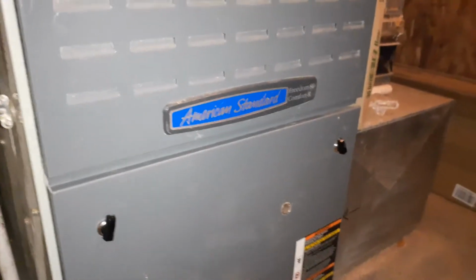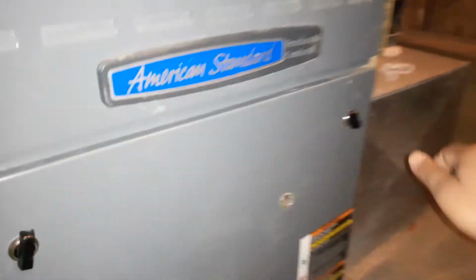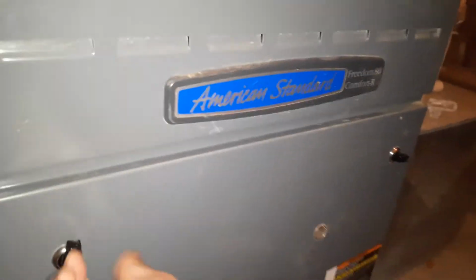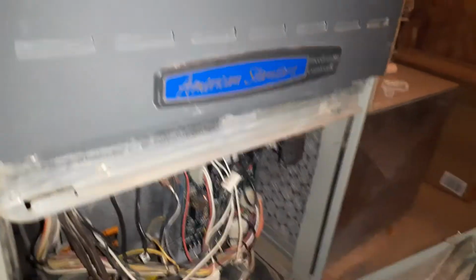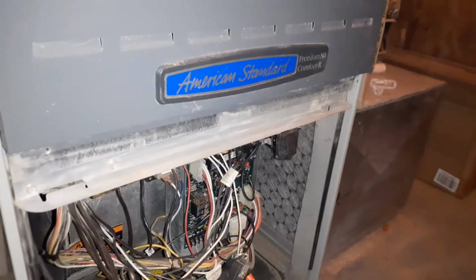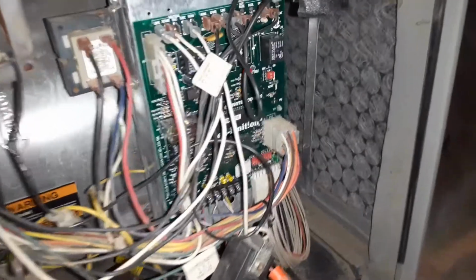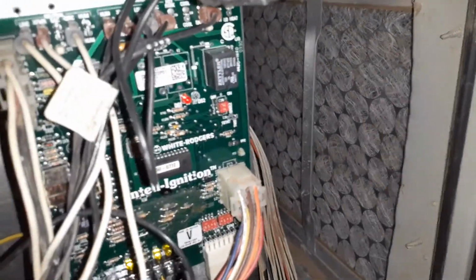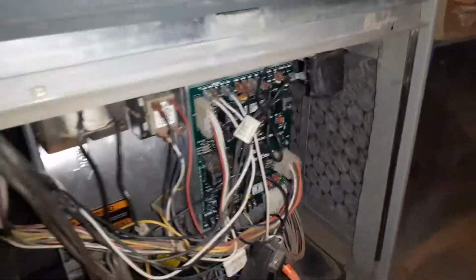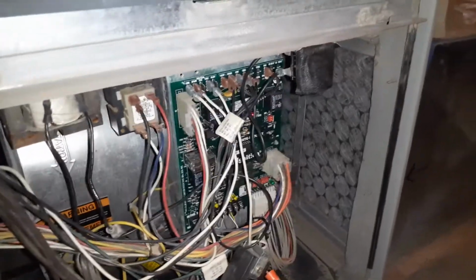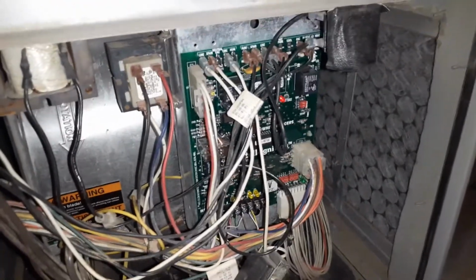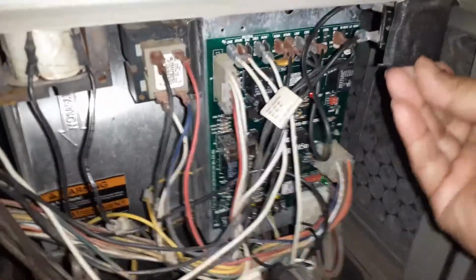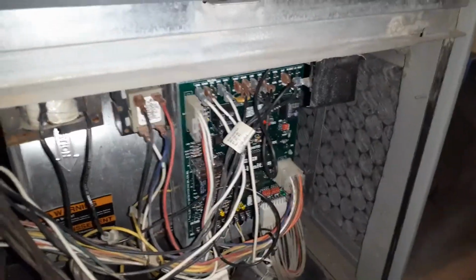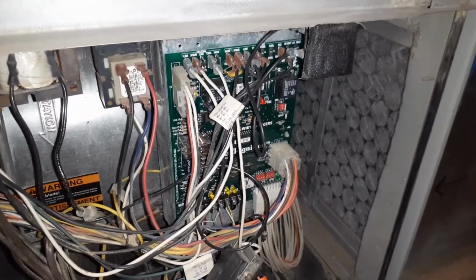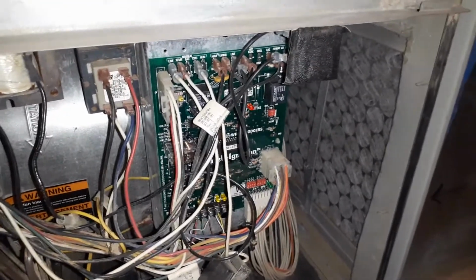After I replaced the circuit board, I'm going to open the furnace door here. The circuit board was replaced, and you will find a video for that. Then it gave me an error code 3, which shows up as 3 blinking lights, and that was with the pressure switch. I was able to clean up the pressure switch. There was water in there, and I have put another video for that one. And then after the pressure switch started working, I got an error code 9. So there were 9 blinks, and then a stop, again 9 blinks.